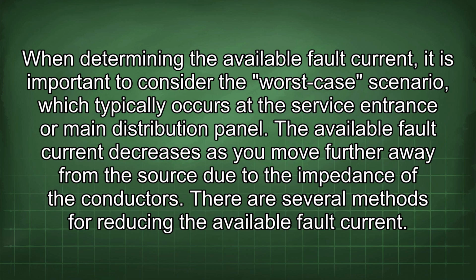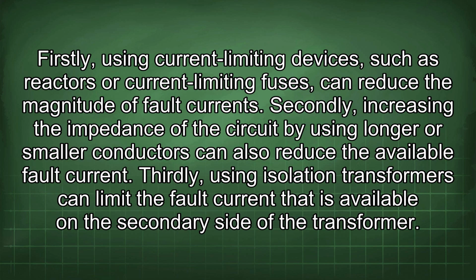There are several methods for reducing the available fault current. Firstly, using current-limiting devices, such as reactors or current-limiting fuses, can reduce the magnitude of fault current. Secondly, increasing the impedance of the circuit by using longer or smaller conductors can also reduce the available fault current. Thirdly, using isolation transformers can limit the fault current that is available on the secondary side of the transformer.